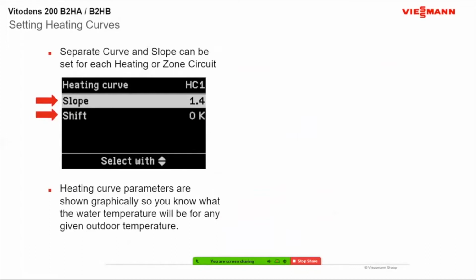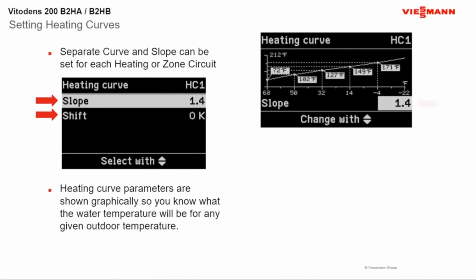So with our boiler, it comes with a slope and a shift. Just be aware that all our boilers are defaulted at the 1.4, as well as our fixed set points pretty close to that as well, because in Germany the law is that they cannot exceed 167 degrees. So that's why our boilers do come defaulted at about the 1.4 heating curve. So if you want a warmer heating curve, you can adjust it there. And then the shift, we're going to talk about that now. We're going to talk about heating curves and slopes and shifts.